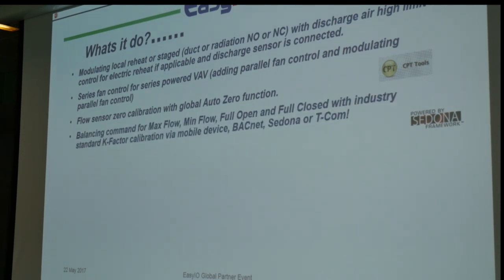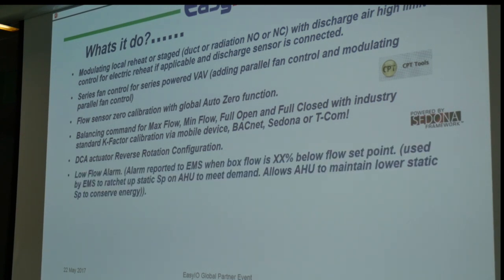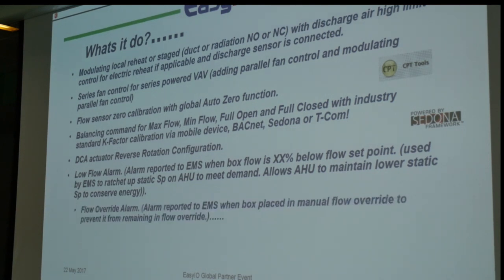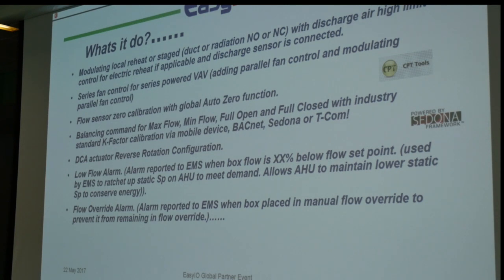Flow sensor zero calibration, balanced via standard ASHRAE K factor, right? That's the standard universal way of balancing. Low flow alarm, that's great for the EMS, and typically the air handler monitors that, so that the air handler can maintain a lower static than what it was set for, and then ratchet up as it gets low flow alarms for one or more boxes to then meet that box, and then later on it can bank back down again to conserve more energy.